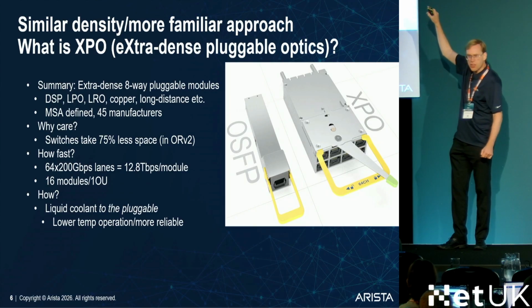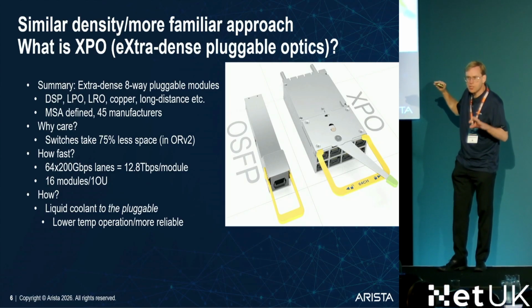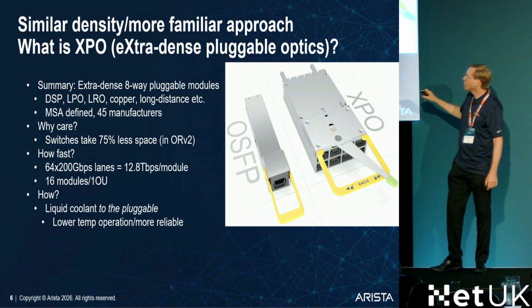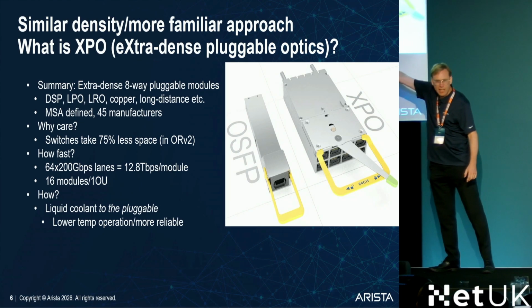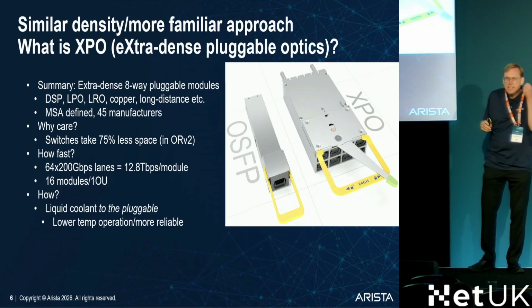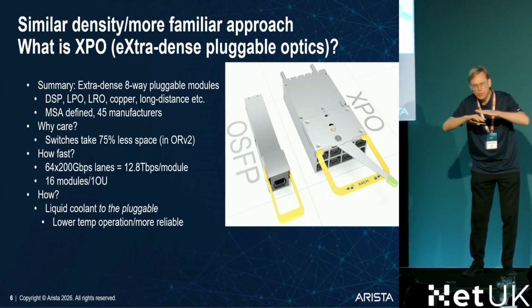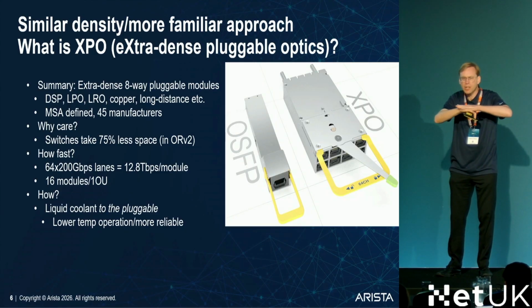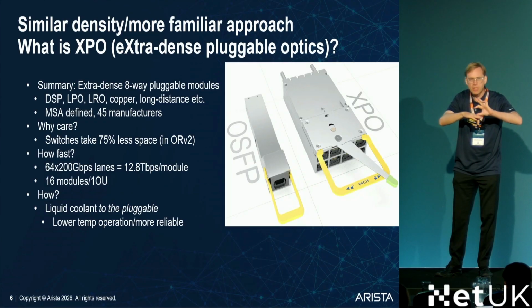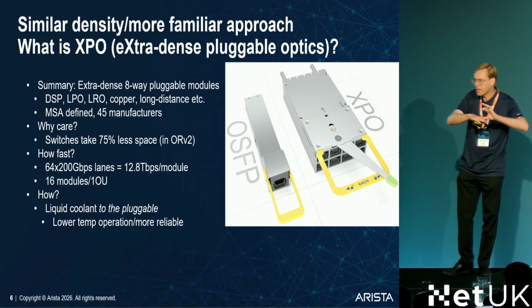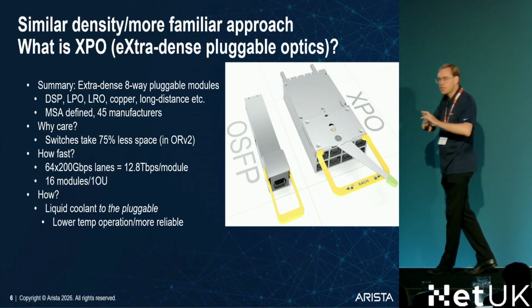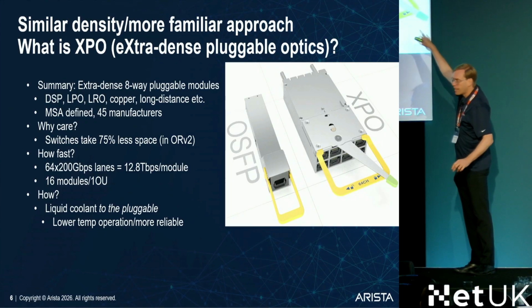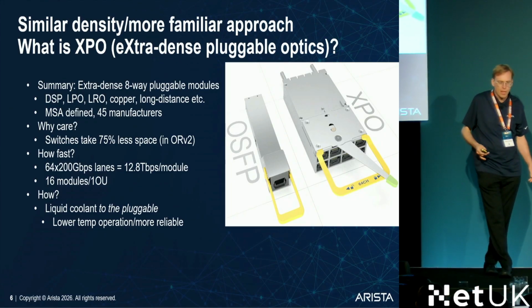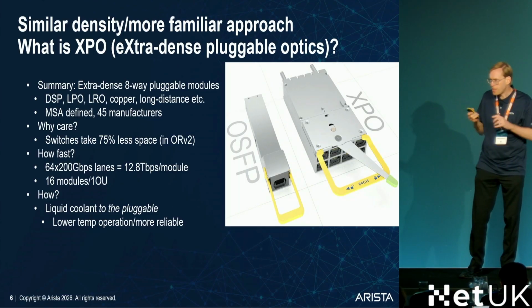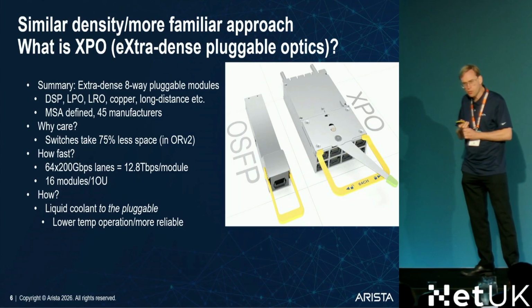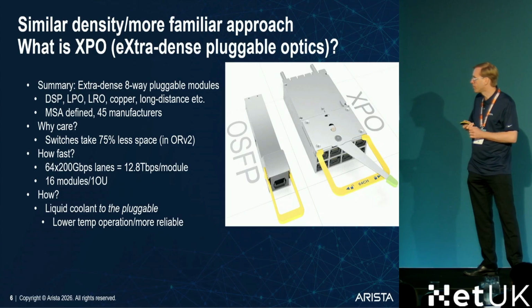This is putting the liquid directly into the module. Half the problem with these things is we have to get the heat out of them, and even with liquid cooling, you have to have an interface between a cold plate and the pluggable, and that interface is only ever so good. This time, we put the liquid directly into the pluggable. That saves a lot of space, but more to the point, it runs cooler and makes it more reliable.